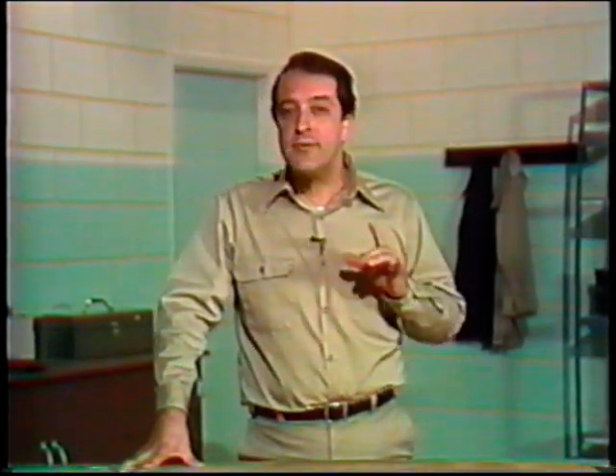Well, we've shown how a synchronous motor operates at synchronous speed. In the next segment, we're going to show you what occurs when load is added to a synchronous motor and what happens when the strength of the electromagnetic field of the rotor poles is varied. We're also going to show you how a synchronous motor can be used to improve the electrical efficiency of an industrial operation. But for right now, take the time to review this information in your text.